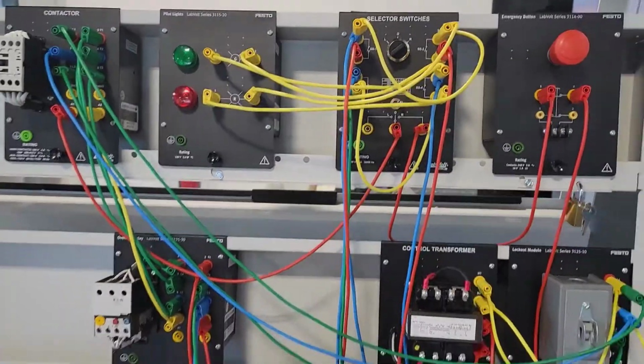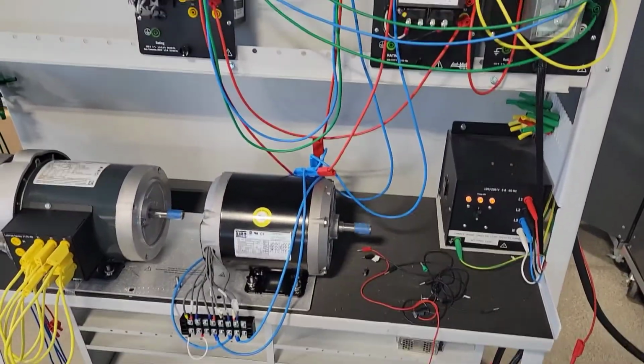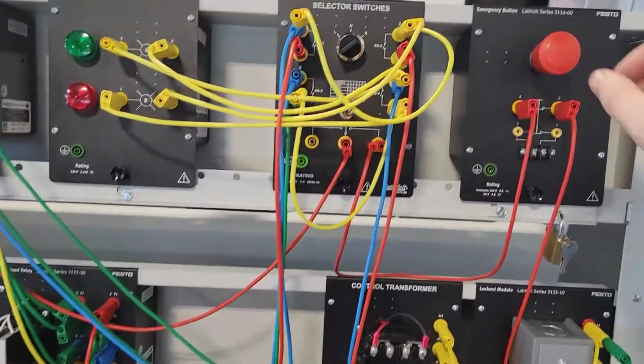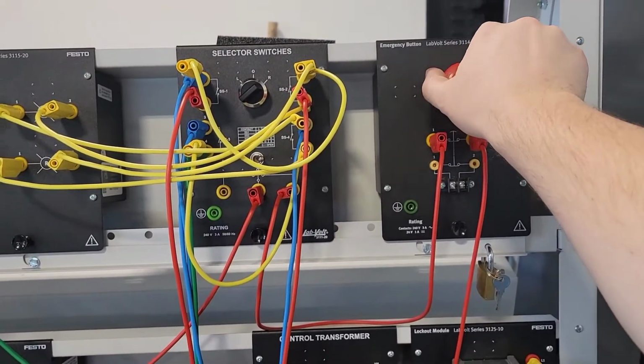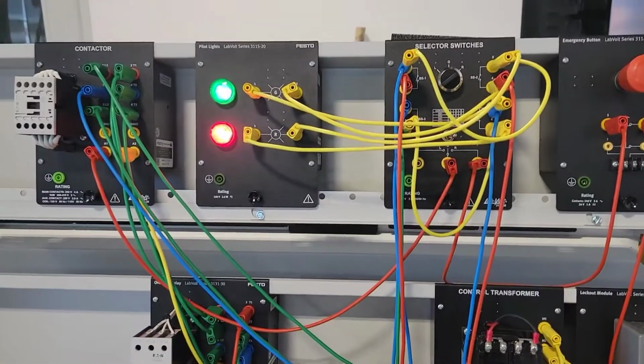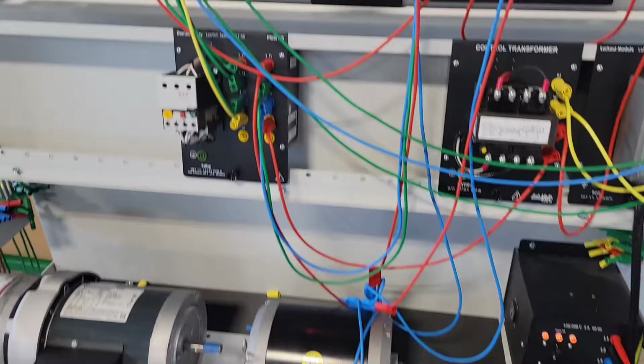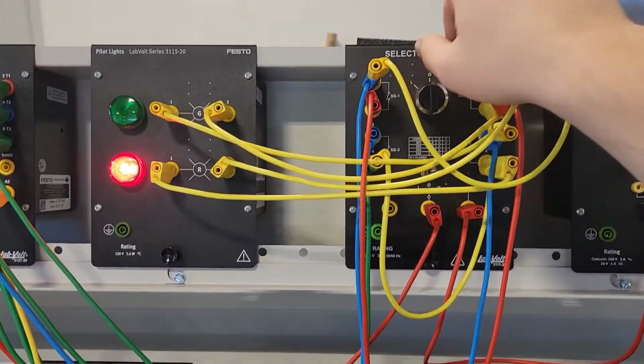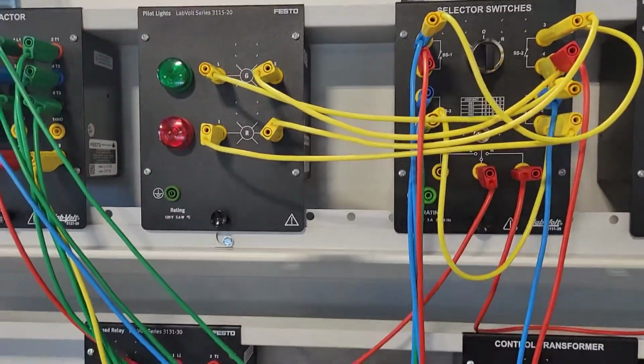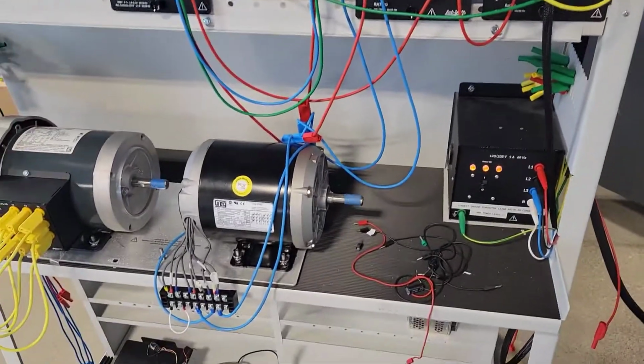E-stop works, everything's off. And because it's a two-wire system, when the e-stop is let off, the motor comes back on, and that is the two-wire system.